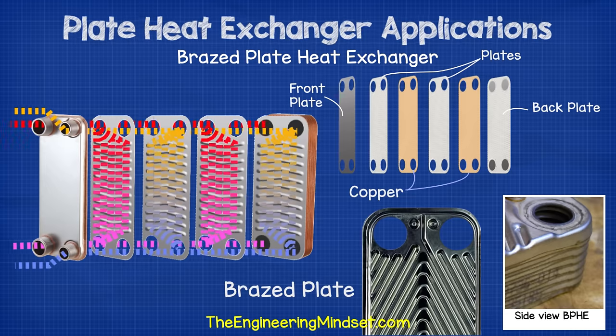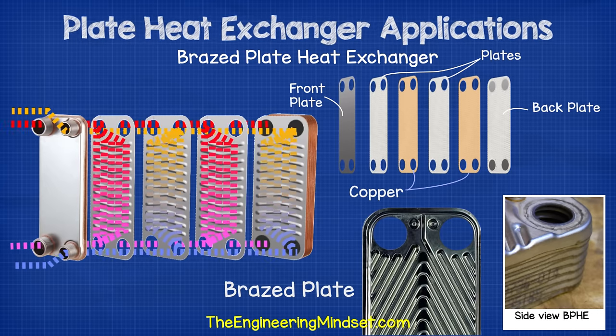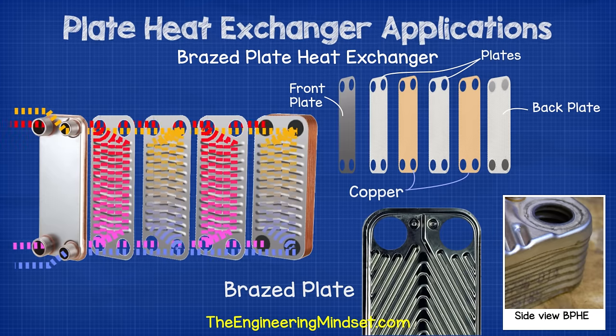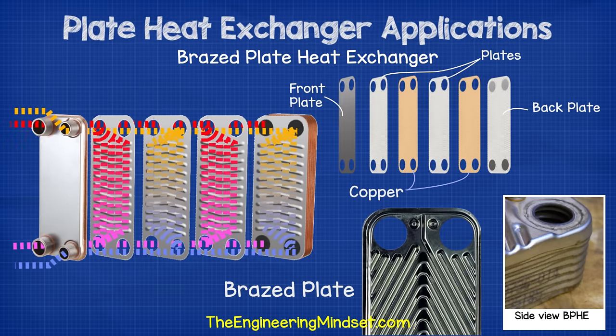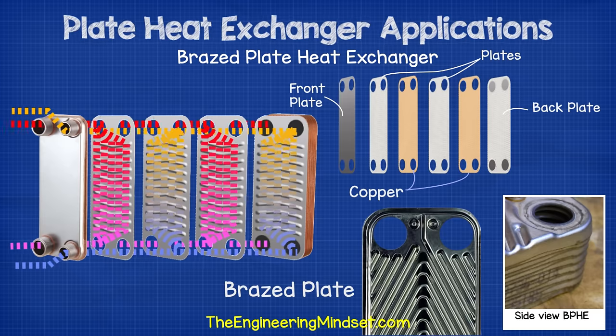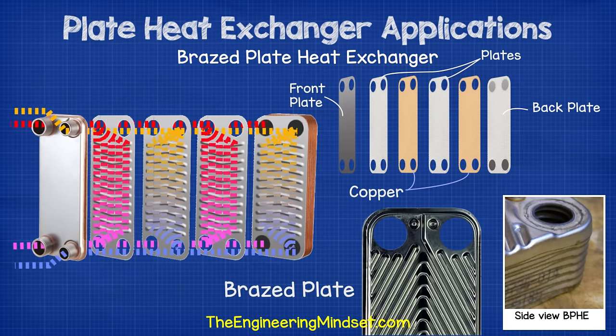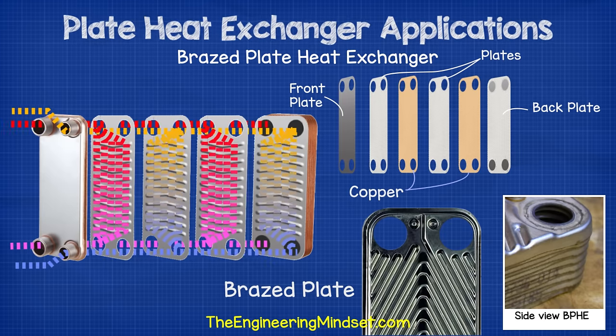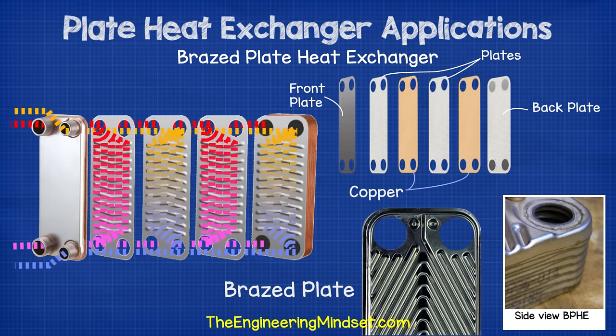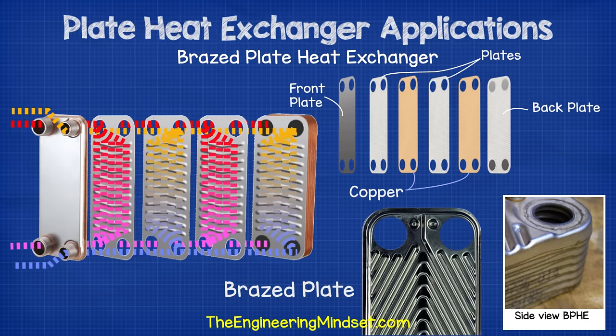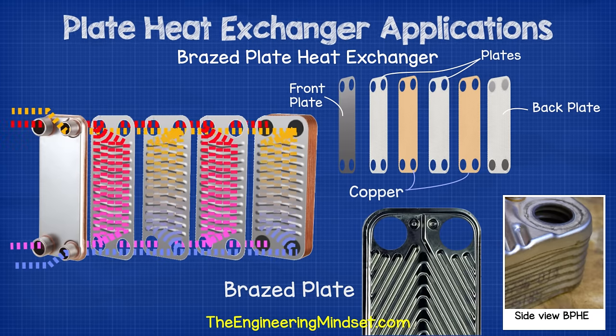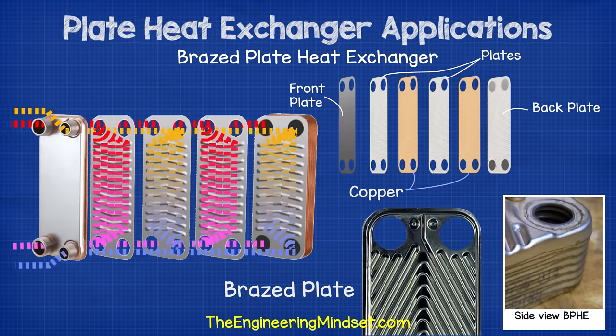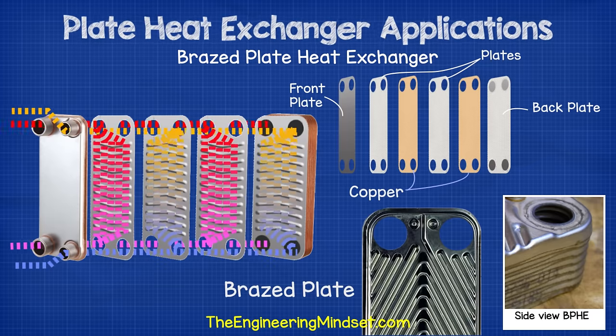Brazed plate heat exchangers are typically used in smaller applications, although in recent years larger units are being produced and applied to industry. These heat exchangers also use thin plates of metal to separate the fluids, but the plates are brazed together to completely seal the unit — no gaskets are used. The brazing and alignment of the plates forms the seal and dictates which channels each fluid can flow into. The plates and casing are typically made from stainless steel, while the brazing is usually copper, though materials vary depending on the fluid used.